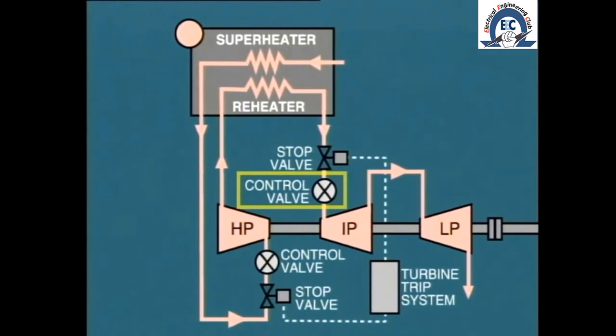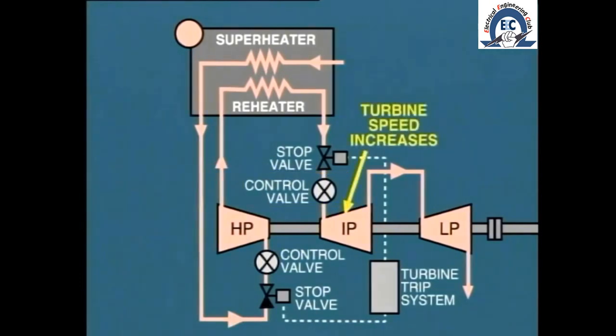However, in the case of a partial load, perhaps due to a transmission line trip, operation of the main steam control valves by governor action may not be sufficient to hold the turbine speed down. Again, this is because of the entrained reheat steam continuing to pass for a few minutes through the intermediate and low-pressure turbines. The intercept valve prevents this.